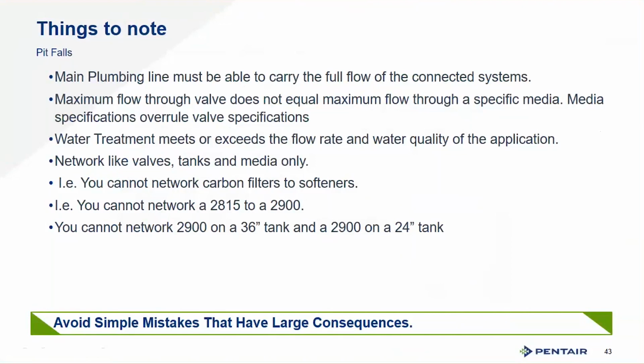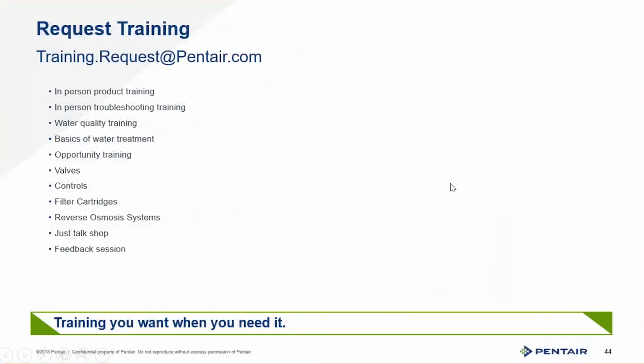Network like valves, tanks and media only. You can't network carbon valves, carbon filters or softeners. You can't network 2815s to 2900s. You cannot network a 2900 on a 36-inch tank with a 2900 on a 24-inch tank. You need to network like valves with like tank size with like media. There are some other opportunities. We're just scratching the surface here.